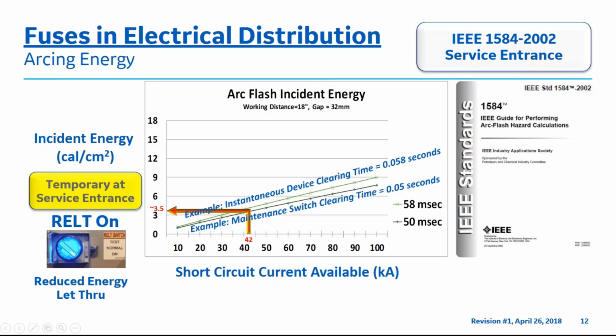As a side note, please remember that if a person unfortunately witnesses a plasma burst of energy of an arcing event of 1.2 calories per centimeter squared, it is enough energy, along with the copper or aluminum shrapnel that would travel with an explosion, that a person would experience a second-degree burn along with potential hearing damage if no PPE, or personal protective equipment, is worn around a power distribution system. Please take every precaution to always uphold electrical safety and wear proper PPE as you enter and work on energized equipment in electrical rooms.